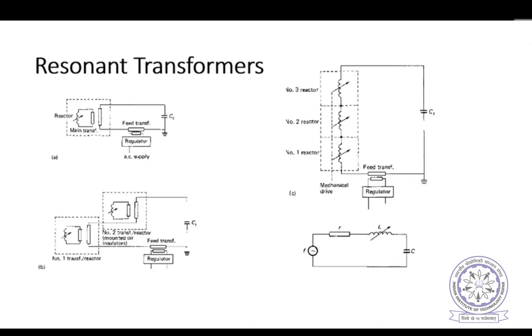In the same way, this is the feed transformer and this is the test object. The test object is always capacitive in nature. So what you do is, we have to change the inductance here in such a way that resonance is achieved. The resonance is intentionally achieved here to generate high voltages. But how to achieve the resonance? You have to change an inductance.